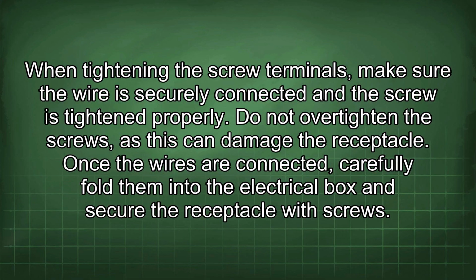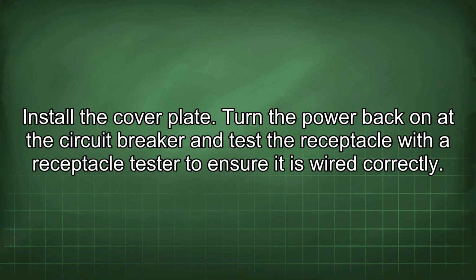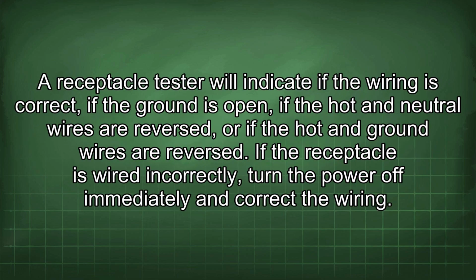Once the wires are connected, carefully fold them into the electrical box and secure the receptacle with screws. Install the cover plate. Turn the power back on at the circuit breaker and test the receptacle with a receptacle tester to ensure it is wired correctly. A receptacle tester will indicate if the wiring is correct, if the ground is open, if the hot and neutral wires are reversed, or if the hot and ground wires are reversed. If the receptacle is wired incorrectly, turn the power off immediately and correct the wiring.